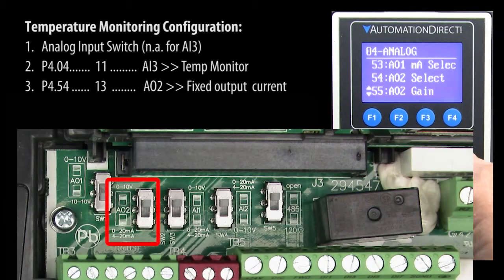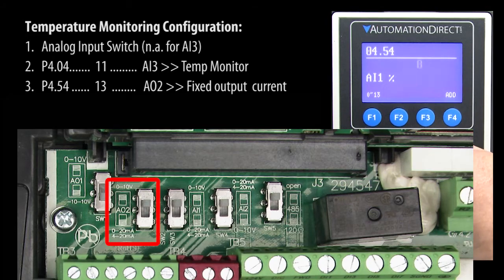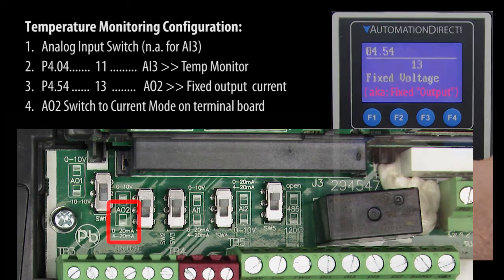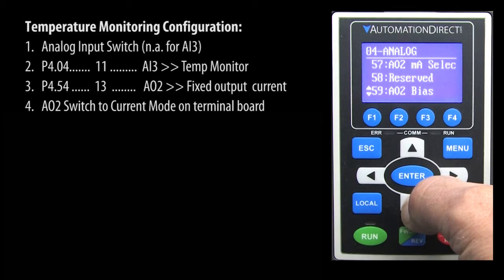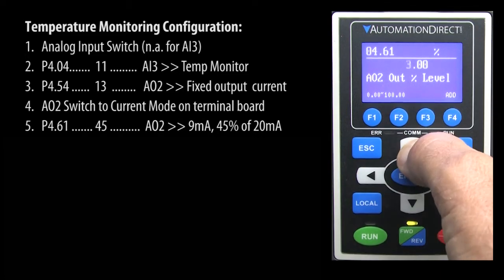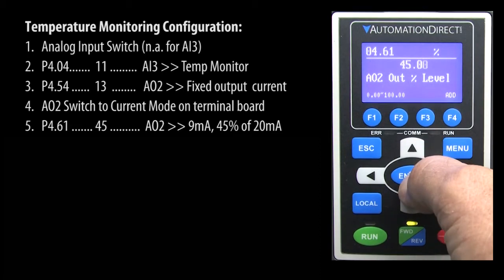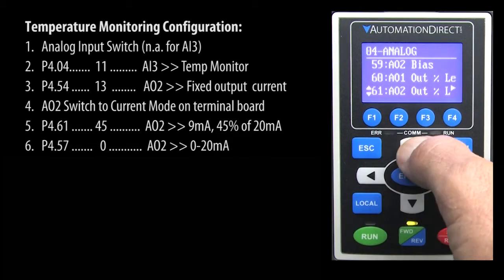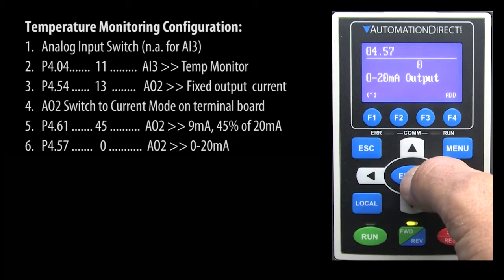Analog output number 2 needs to output a fixed current, so we need to make sure his switch is set for current output. And we want to set the fixed output at 9 mA, which is 45% of the 0 to 20 mA range. Of course, make sure analog output 2 is set for 0 to 20 mA, not 4 to 20 mA.